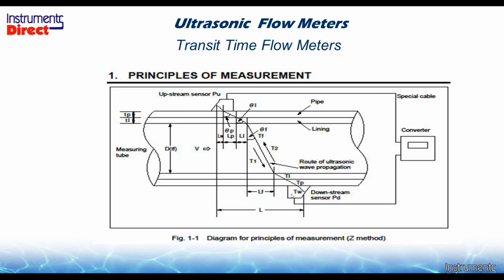Now, the ultrasonic transit time equation: the core equations are the same, but they have many more additions to the equation to make it a little more accurate, a little more user-friendly. As you can see, what you get to use today is a final device with drop-down menus to do everything for you. Go backwards 10, 20, 30 years ago, we had a big black suitcase that you had to carry around, and you had to program all these different variables and look at the math behind it. And that's what I'm going to say: an ultrasonic transit time flow meter is a big math equation.